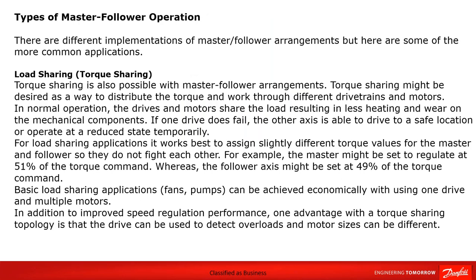So the different types, we'll just look at a couple. There's different implementations of master follower arrangements, but let me give you a run through a couple of the most common applications. Load sharing, torque sharing, which you've heard me mention. Torque sharing is also possible with master follower arrangements, and it might be designed as a way to distribute the torque and work through different drivetrains and motors. In normal operation, the drives, the motors, actually share the load, resulting in less heating and wear on the mechanical components, as I've mentioned before.